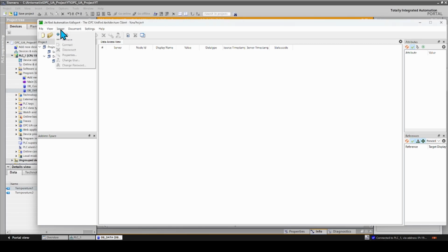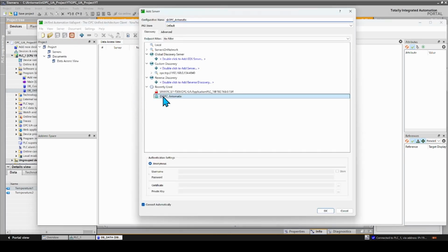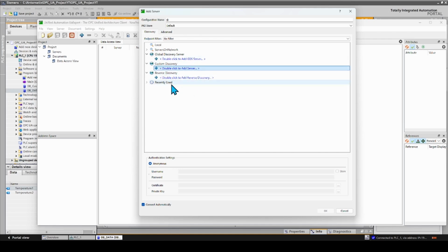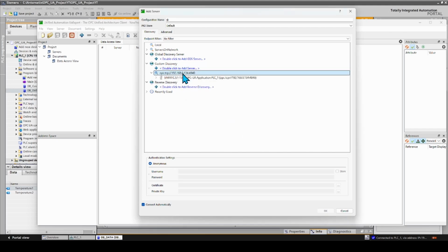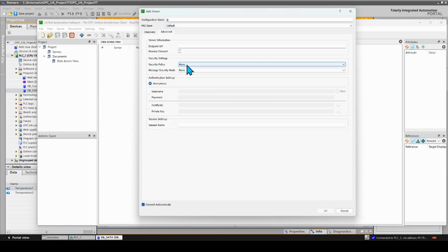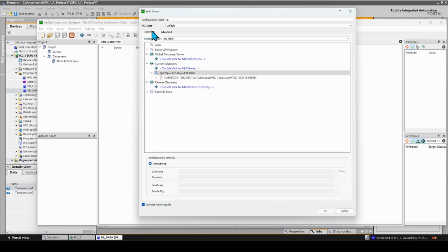Next step is to test our server with OPC UA client. For this purpose, we use free UA Expert software. We will add now our PLC server address. We will not use secure connection and access it using anonymous user. I will still configure security policy because I often use secure user connection, which I will show in future videos. I will give a name to our connection and save the config.